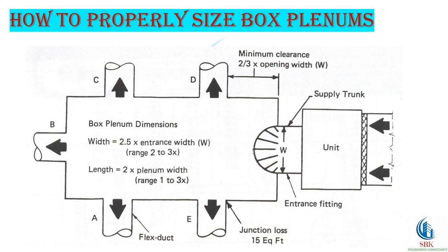Optimum plenum width is 2.5 times the width of the connecting supply trunk, or simply the width of the entrance opening. Box plenum width may vary from 2 to 3 times the opening width. The preferred box plenum length is 2 times the plenum width, but may vary from 1 to 3 times the plenum width. Note the minimum clearance requirement between the first branch takeoffs and the entrance to the box plenum.